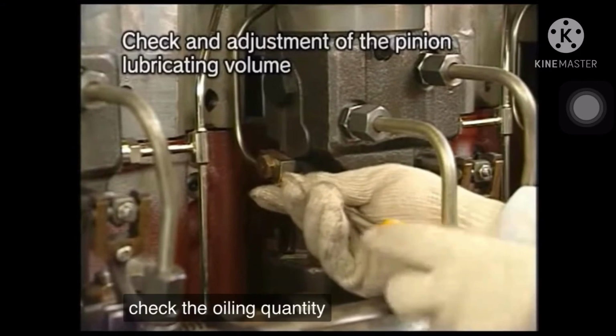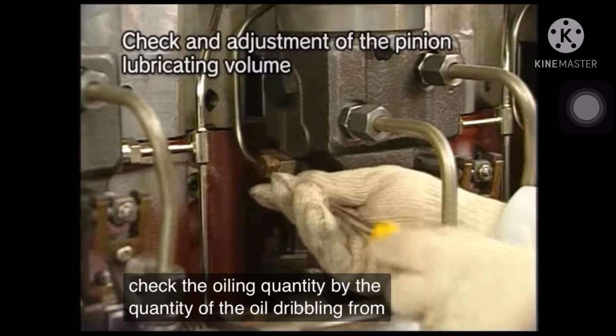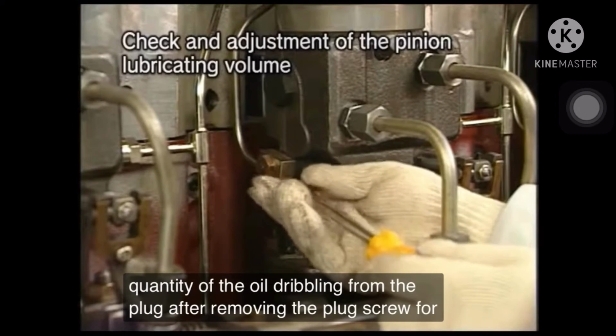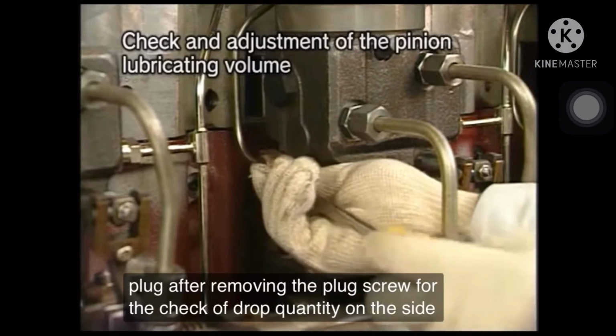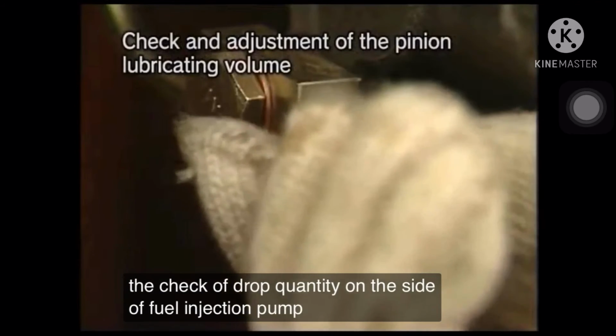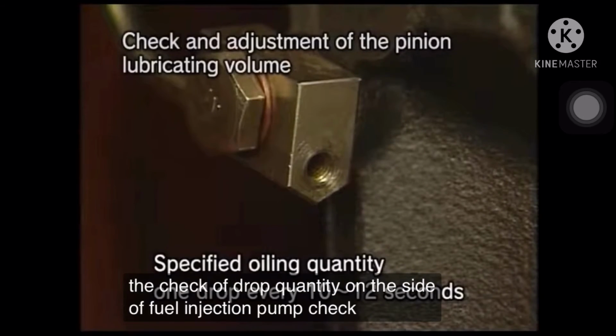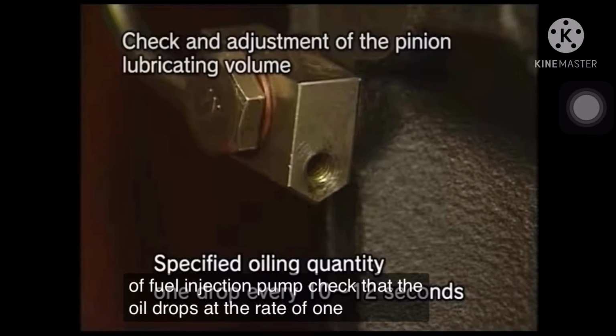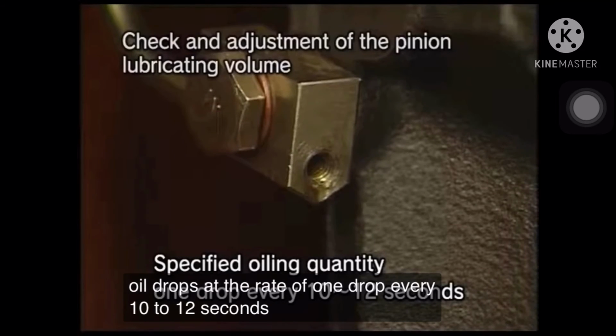Check the oiling quantity by the quantity of the oil dribbling from the plug after removing the plug screw for the check of drop quantity on the side of the fuel injection pump. Check that the oil drops at the rate of 1 drop every 10 to 12 seconds.